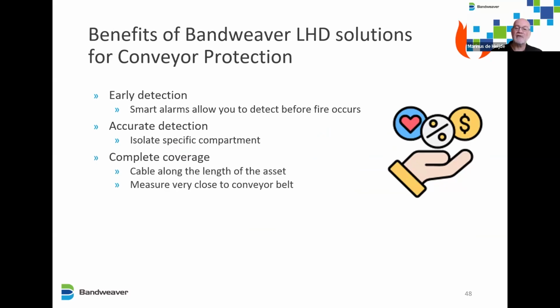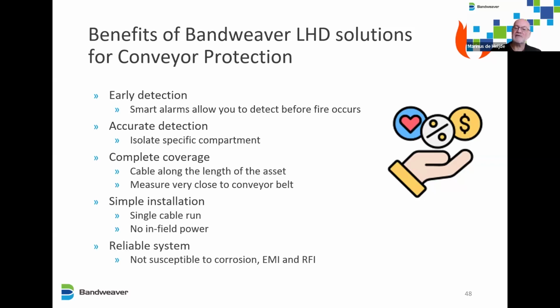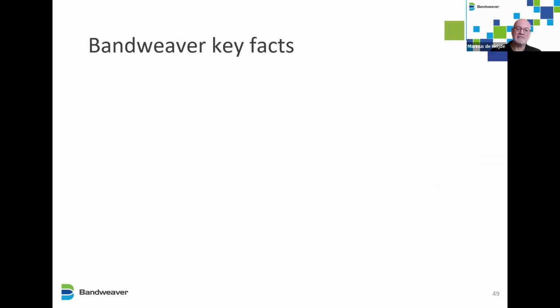It also gives a complete coverage. Cable runs along the length of the asset. We can measure very close to the conveyor belt itself. And it's a very simple installation. Single cable run with no infield power needed. It's only the cable that you need to install, and then from the unit you send a laser light through it. And it's a very reliable system which is not susceptible to corrosion, electromagnetic interference, or radio frequency interference.